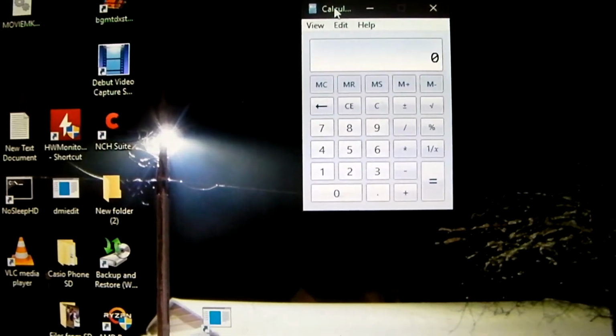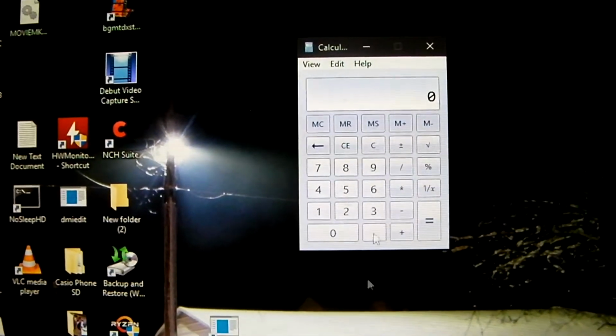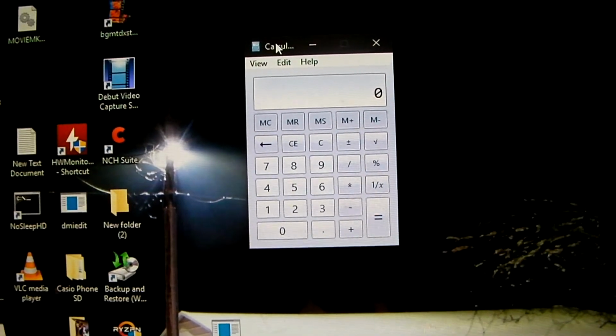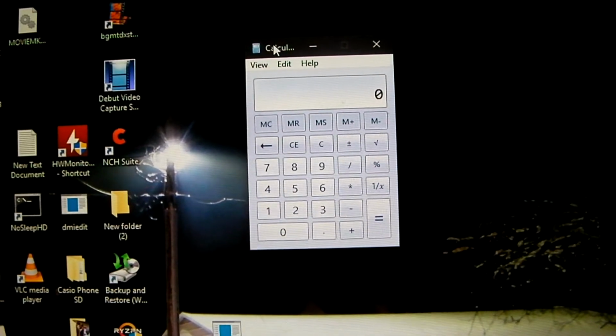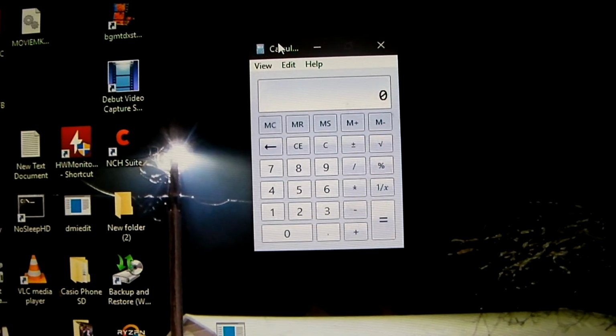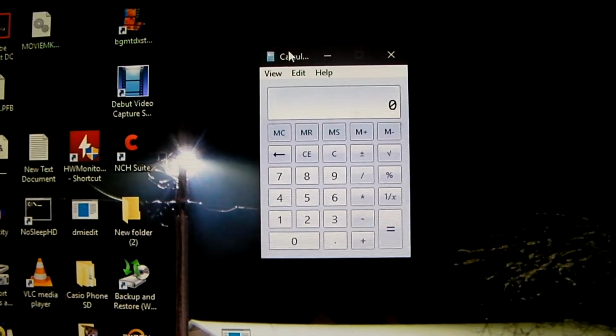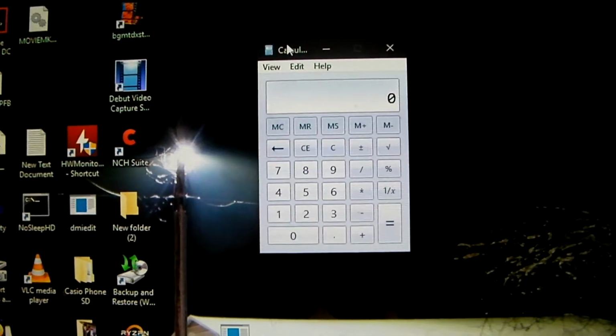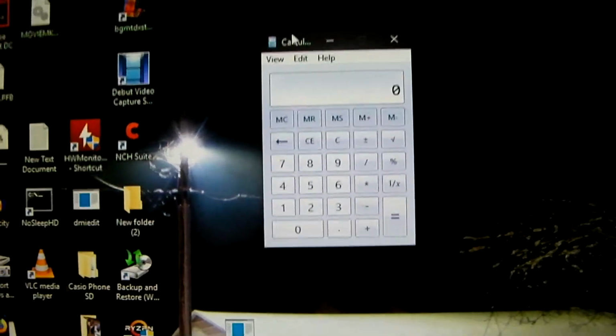I tell you, just for example, I got a calculator pulled up here. Let's say your heat pump defrost control is set to 30 minutes, which is like I had mentioned outside. From the factory, they're mostly set like that, and they rely on the installer to set them properly, but many installers simply don't do it.